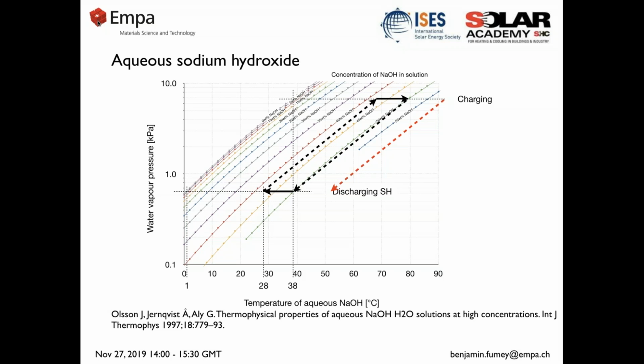Here, just to point out, you see in the red dashed line the fact that in our case with sodium hydroxide, we do not want to go beyond 58% because we have a liquid sorption system, and sodium hydroxide tends to crystallize above 58% at room temperature. So we already see here with these defined temperatures a slight limitation in our case with sodium hydroxide.